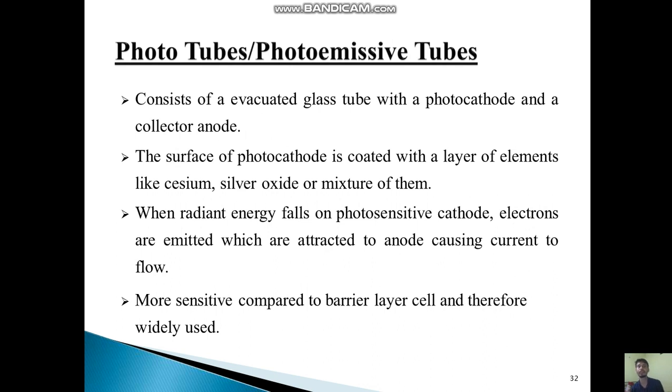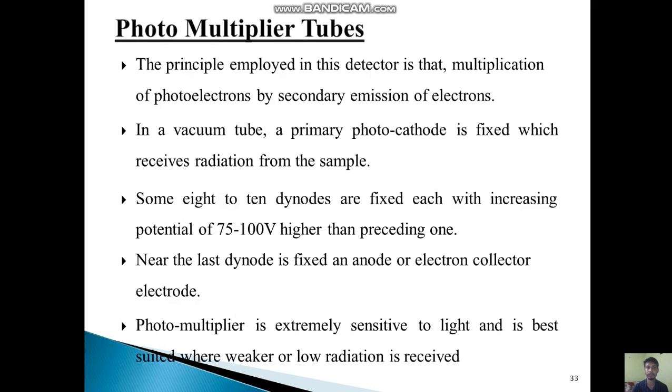The photo tube consists of an evacuated glass tube with a photocathode and a collector anode. The surface of the photocathode is coated with a layer of elements like cesium, silver oxide, or a mixture of them. When radiant energy falls on the photosensitive cathode, electrons are emitted which are attracted to the anode, causing current to flow. This is more sensitive compared to barrier layer cells and therefore widely used.